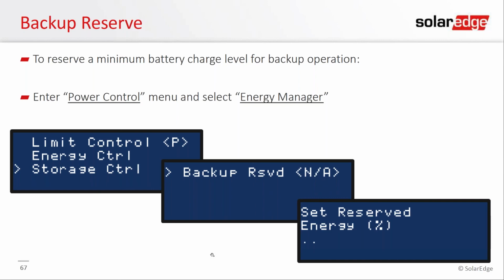Yes. Okay. What voltage is the battery wired to? So the battery is DC coupled, and so our optimizers fix the DC voltage at 350 volts for the standard inverters. However, with StorEdge, that operates at 400 volts. So the battery voltage nominal is 350 to 450, typically operating around 400.